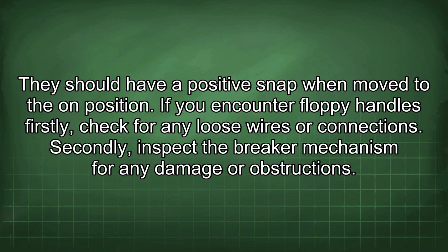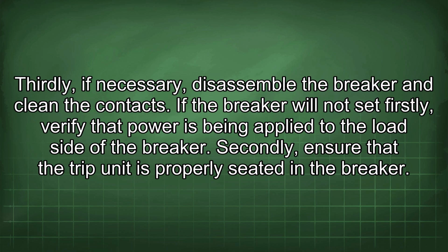If you encounter floppy handles, firstly, check for any loose wires or connections. Secondly, inspect the breaker mechanism for any damage or obstructions. Thirdly, if necessary, disassemble the breaker and clean the contacts.